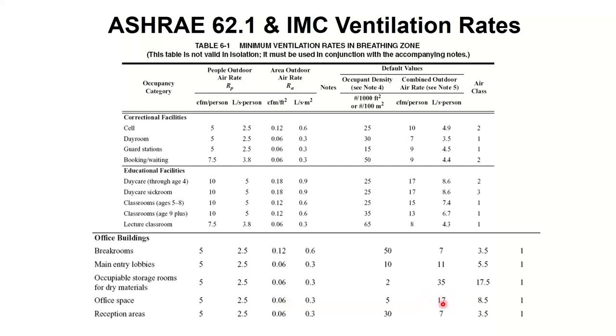Now, if you have more or fewer cubicles in the room, that number 17 would be different. But the 5 per person and the 0.06 per square foot are what you're looking at from a code requirement. The reason that it's split was to make demand control ventilation easier. So we can modulate the people portion, but we can't modulate the building portion, because the building portion is caused by VOCs and furnishings and carpeting and all that stuff. The per person portion is the amount of people coming in and out of the building, and that we can track with CO2 and decide if we want to modulate that portion or not.